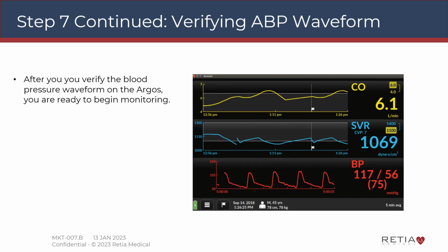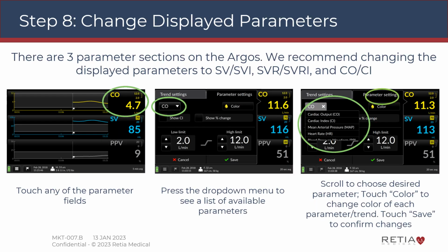After you verify the blood pressure waveform on the Argos, you are ready to begin monitoring. Step 8. Change displayed parameters. There are 3 parameter sections on the Argos. We recommend changing the displayed parameters to SV, SVI, SVR, SVRI, and CO, CI.